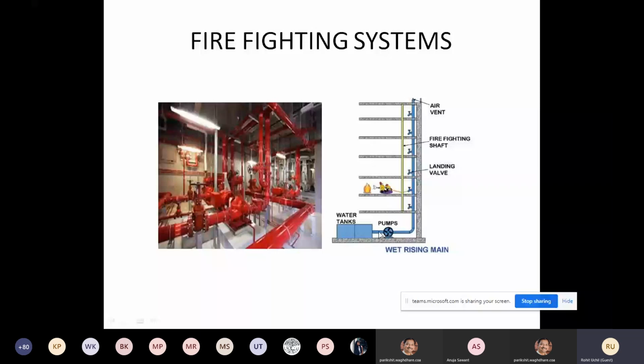supply the water through something called a wet riser. It's called a wet riser because there's always water under pressure in these risers. If you can see, on every floor there is something called a landing valve. Now there are two tap-offs on every floor.